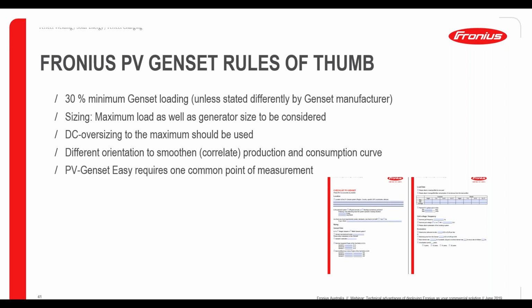In terms of what we call the PV-Genset Easy requirement, that only needs one common point of measurement. There is also an advanced version of our genset controllers. We won't be touching on them today, but there is a possibility to install them, and we can always go through further information later on. In the bottom right-hand corner, we've also got a PV-Genset checklist. This is a viability checklist for working out if it's going to make sense, if the numbers all work out in terms of costings, but also the total setup and calculations between the solar and the genset side of things.